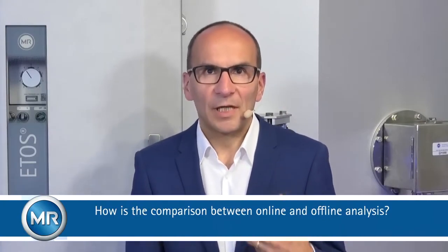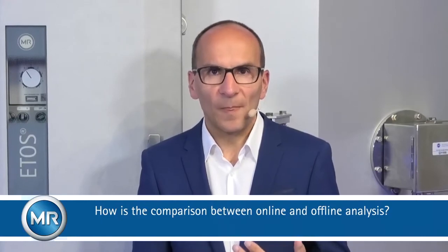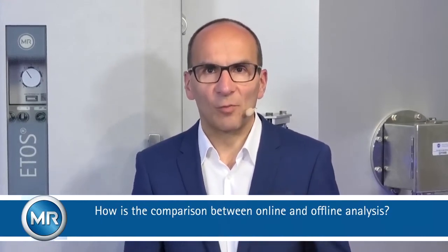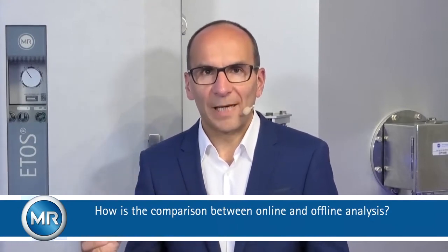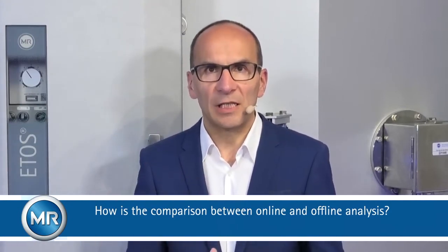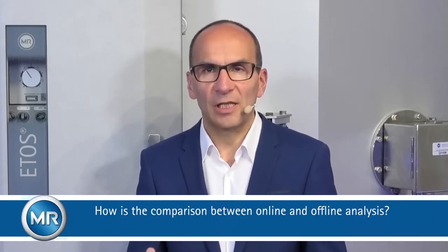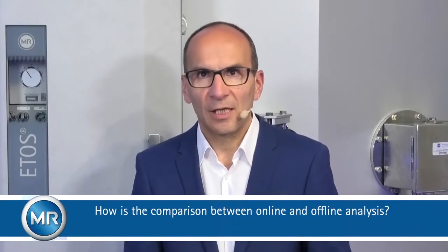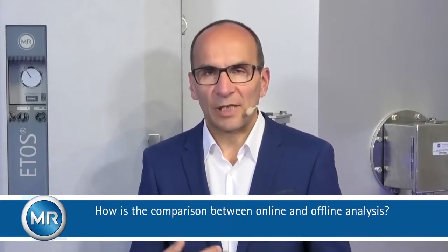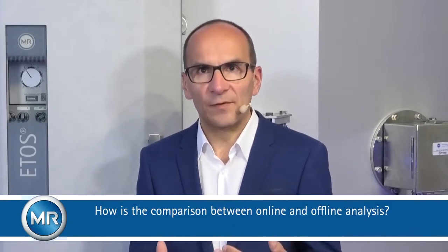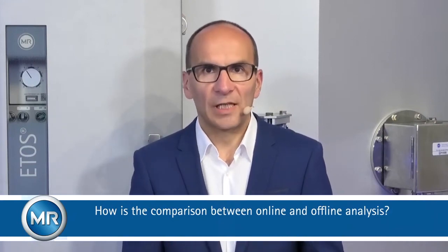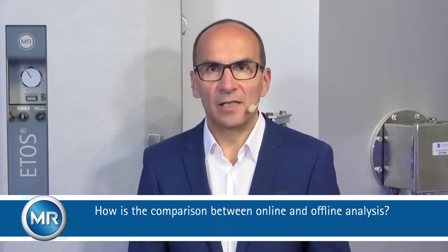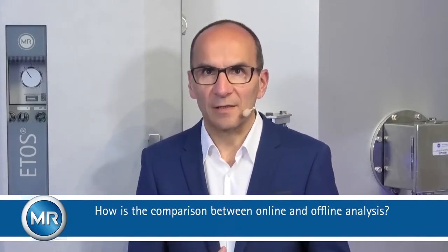MSENSE VAM is an online monitoring tool which compares in real-time operation the pattern of the OLTC noise and vibration against the limit value, which is self-learning. The system recognizes changes, and if the limit value curve is hit or is exceeded, then an event is created.